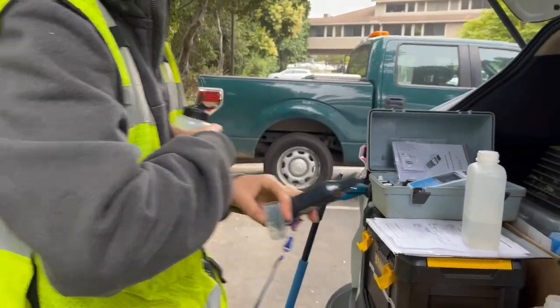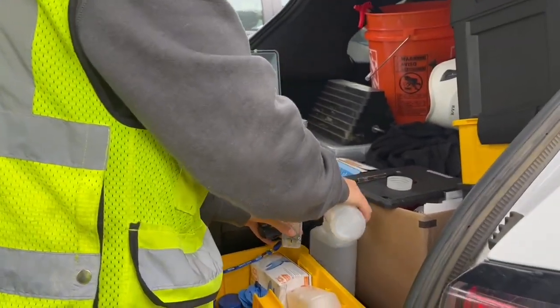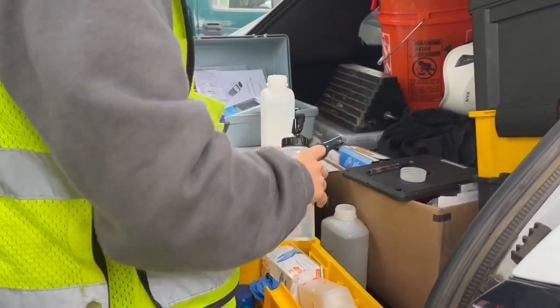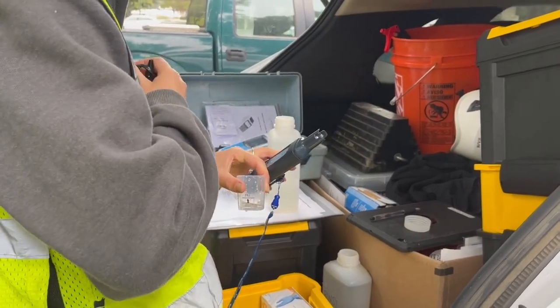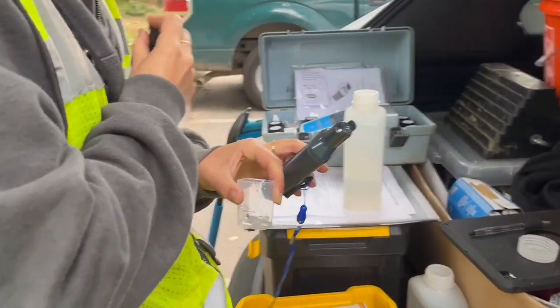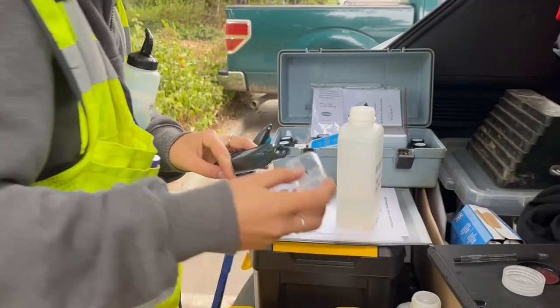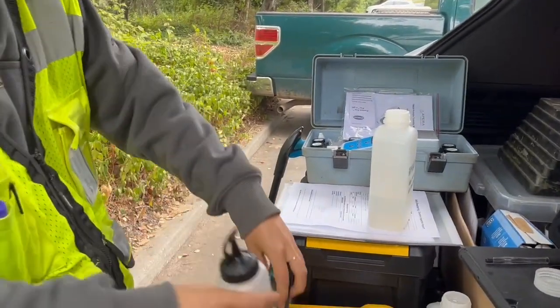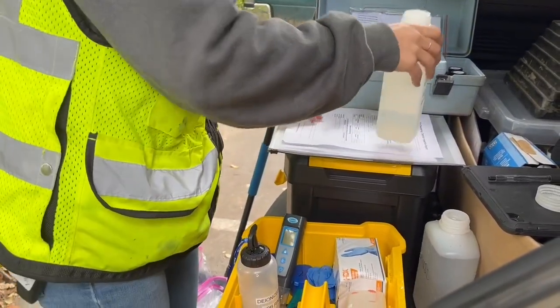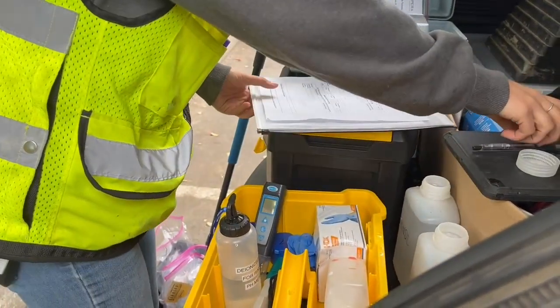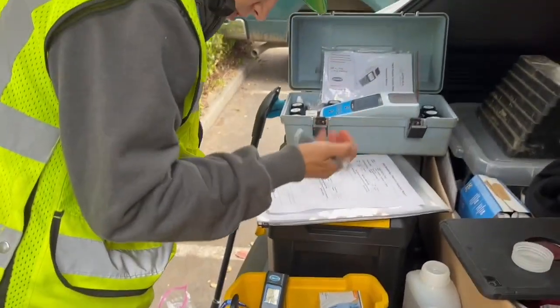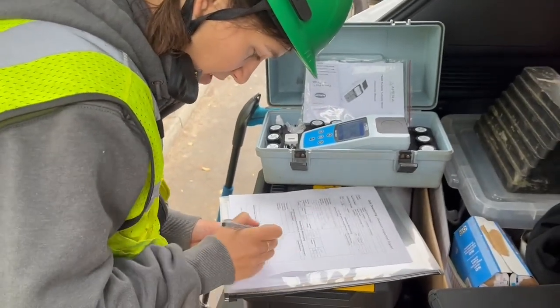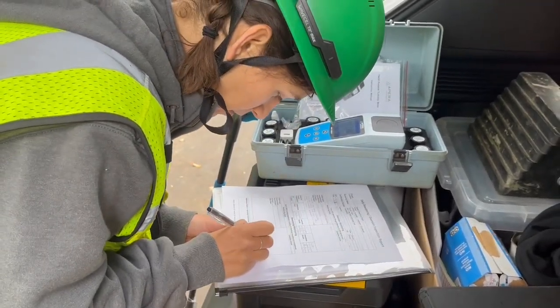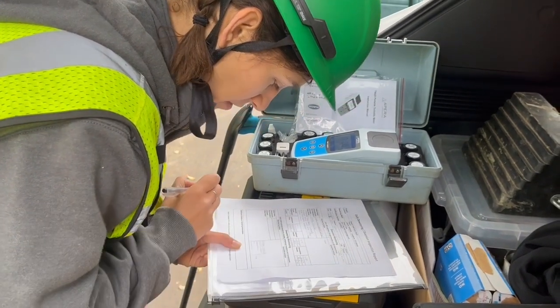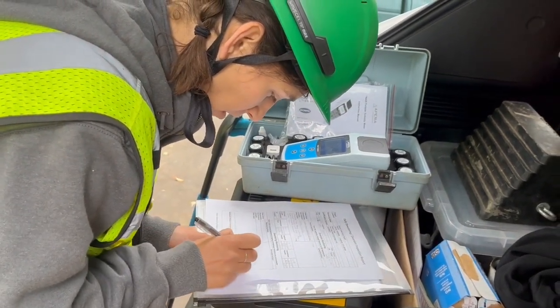Grab again the deionized water solution. Rinse it off, the probe and the container. Cap it, put it away. Now our measurements were 7.9 and 16.0 degrees Celsius. So I'll write that down. Typically, best practice is to take a picture of the reading so that you also have a timestamp of it.